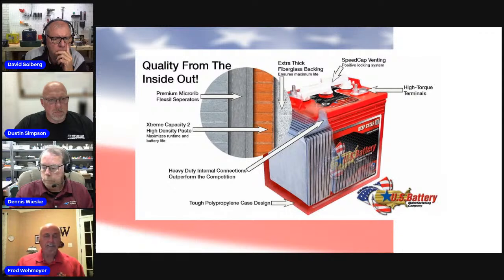Which would be the case if you did that with modern maintenance-free automotive batteries. Beyond that, you'll see some major construction differences: very thick plates on both the positive and negative electrodes, and a Flexsil separator, which looks completely different from automotive battery separators. The premium separators used in deep cycle batteries are made from a rubber compound, purposely used to offset some of the effects of antimony on water loss. These premium rubber separators have components that help reduce the amount of water you have to add over the life of the battery.